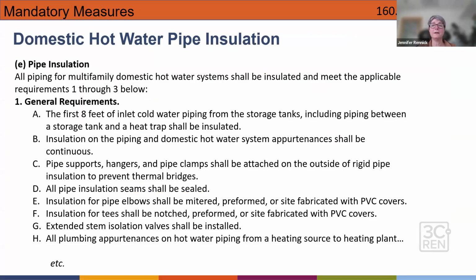Okay, for the mandatory measures under hot water, there's a new section, or really an elaborated section, specifically for hot water piping insulation. For example, the first 8 feet of the inlet cold water piping is also supposed to be insulated, even though we're dealing with the hot water piping. In addition, all of the hot water piping and appurtenances need to be continuous.